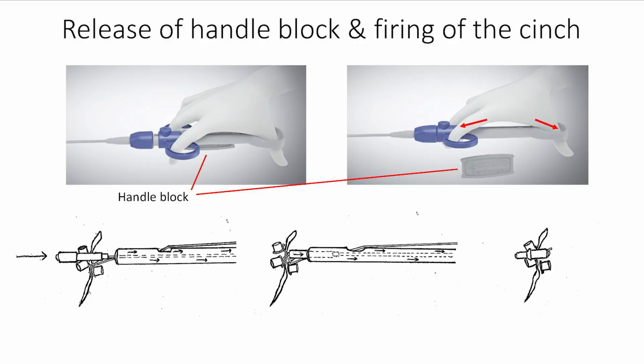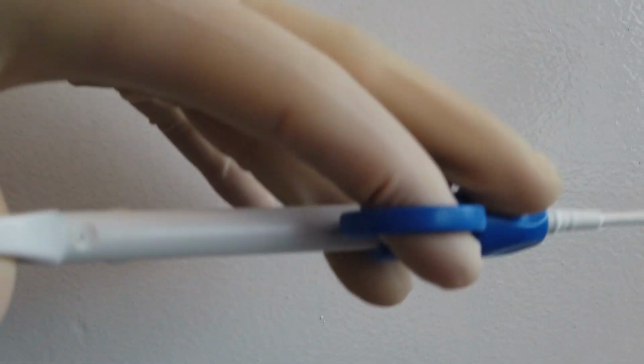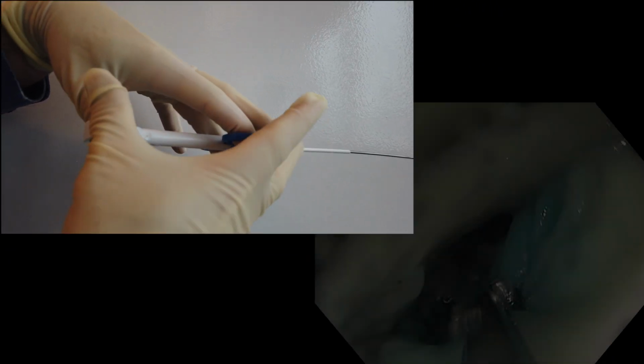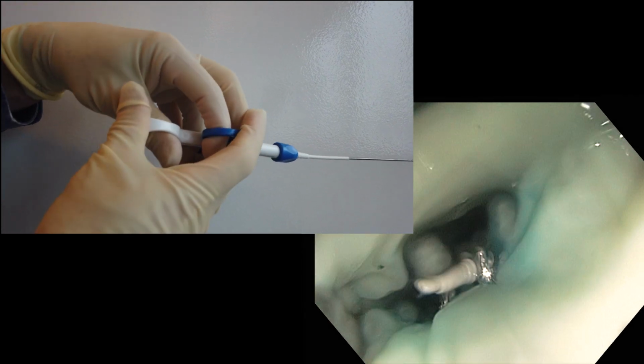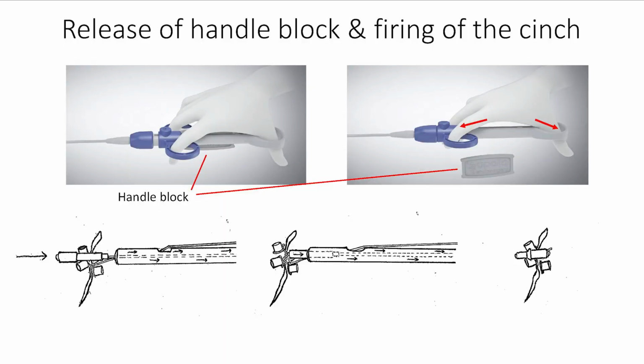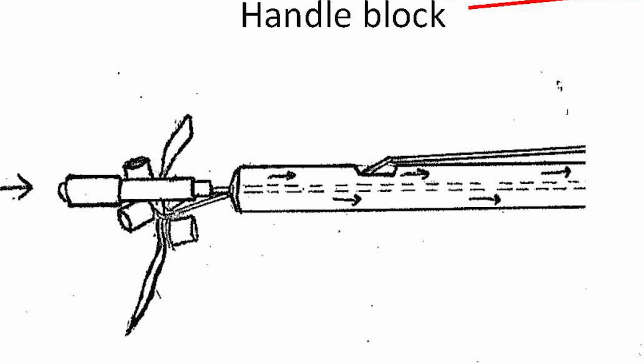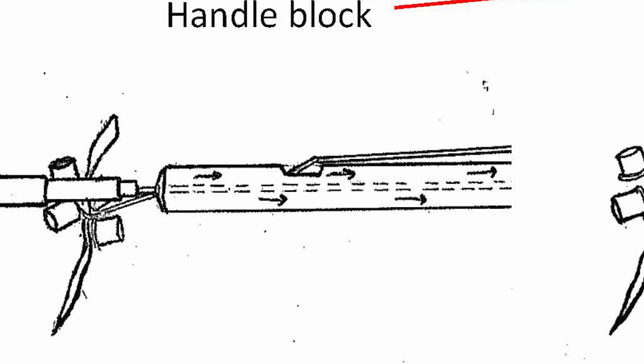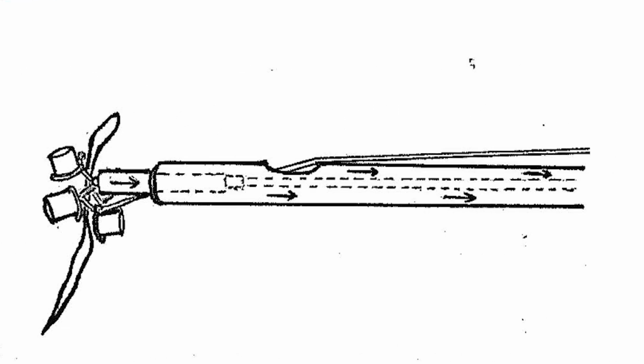When the tacks have been pulled together as tightly as possible and while maintaining tension on the suture, the cinch device is fired by the first assistant who is holding the instrument's handle. Prior to firing the cinch, the handle must be opened a bit to release the plastic block that sits in the handle. After the block has fallen away, the handle is then fully closed, which is best done with 2 hands. This draws the cinch into the hollow tip of the device and then pulls the suture through the cinch, which secures the closure. The device also cuts the suture just beyond the cinch.